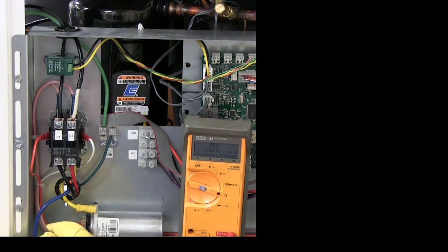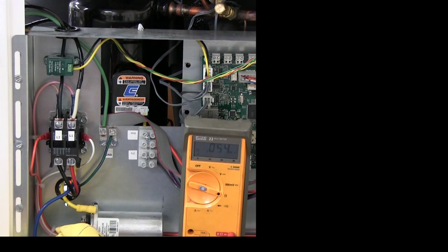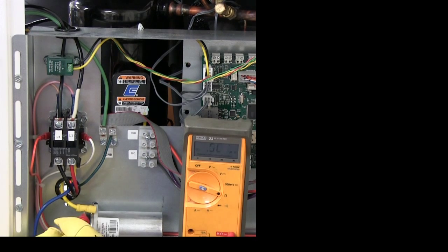As I was saying, the meter is set to resistance. You'll see that when I connect the two leads, the resistance will slowly climb. What's happening is the battery within the meter itself is charging the capacitor. If the capacitor was defective, you would not see the resistance climb. Once it reaches full capacitance, it will actually stop. That's why every time you do the test, you want to make sure that the capacitor is discharged using the leads.